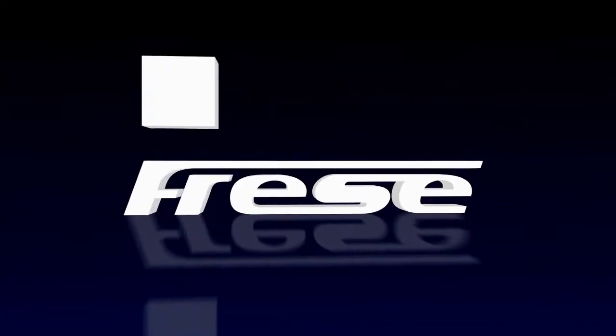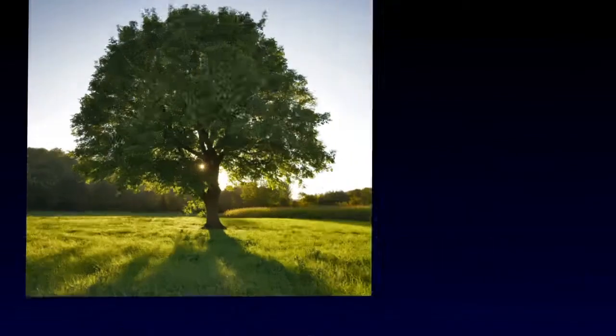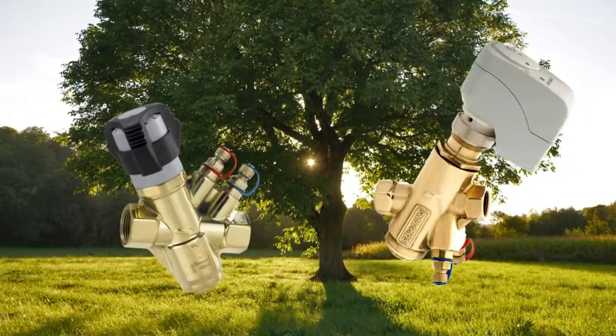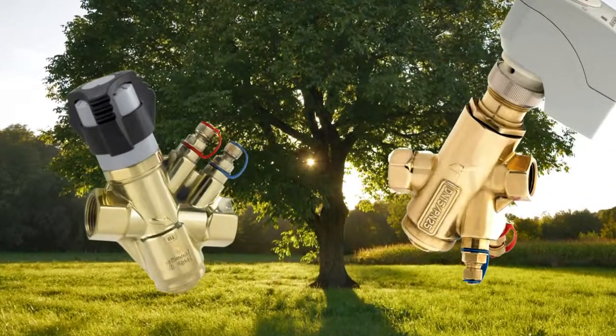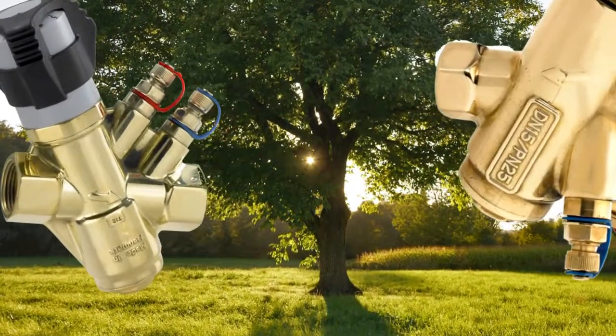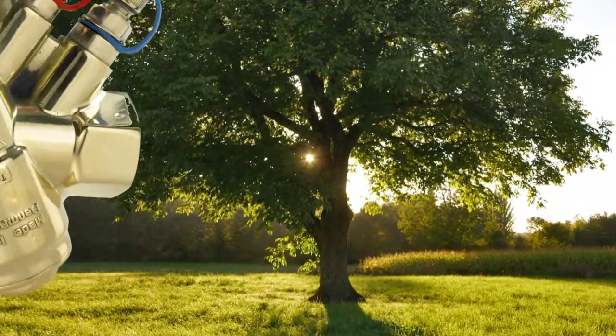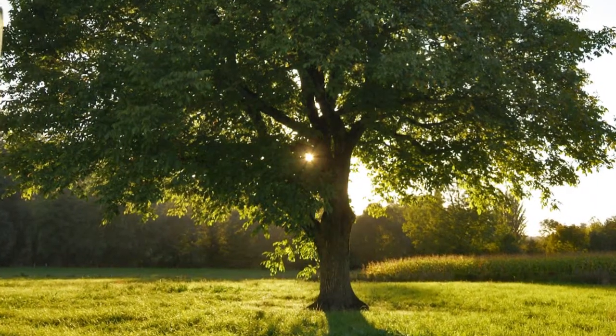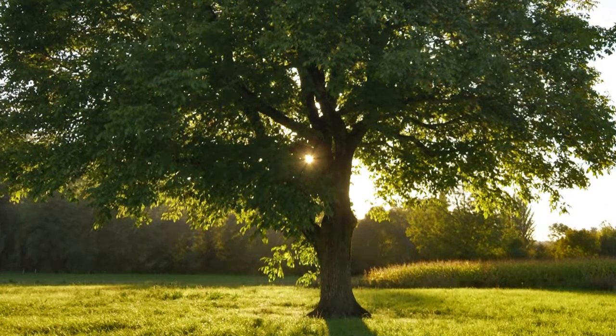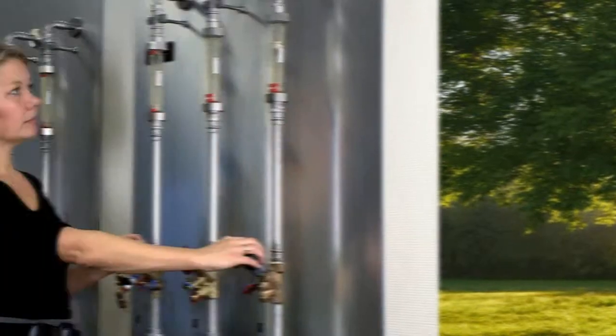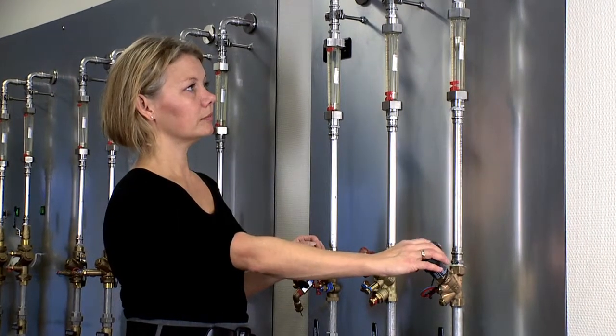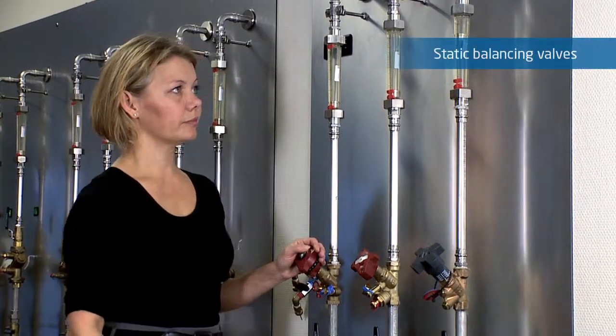This film is about the advantages of using dynamic balancing valves instead of static balancing valves in heating and cooling systems. In short, you can reduce pump energy consumption by up to 50%, as well as save time and contribute to a greener world. Let's first take a look at how to commission a system with static balancing valves.